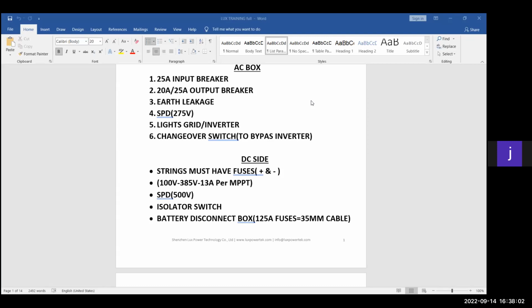So that's why I personally try to put my breakers so that the client can't have that big amount of power flowing through an inverter. It's a 5 kilowatt inverter, and I don't like it when there's more than 5 kilowatts flowing through the inverter. If that's 3 kilowatts that's been charging and 3 kilowatts that's been used in the house for whatever the reason might be, then it will still be a big amount of 6 to 7 kilowatts flowing through my inverter. So that's why I recommended a 25 amp input breaker. But as I said, it's your choice which size you would like to install.